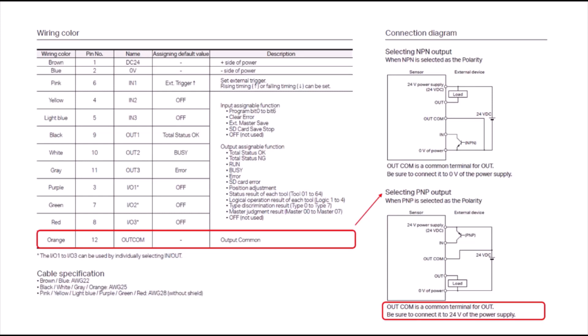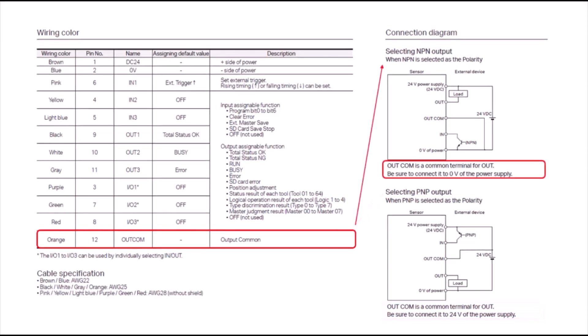Where the orange wire will connect will depend on what polarity you're going to use. If you're going to want a PNP 24-volt output, then your output common would connect to the 24-volt side of your power supply. If instead you are wanting an NPN 0-volt output, your output common would connect to the 0-volt side of your power supply.